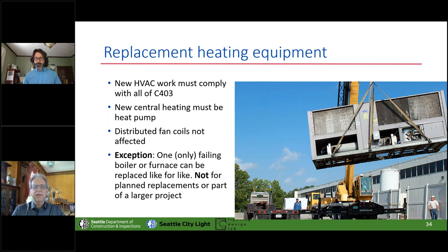For heating equipment, basically anything that's new must meet the new code. And if you replace the central heating system, it's got to be replaced with a heat pump. Now, at least for now, we've said if you've got one of these many Seattle towers with fan coils all around and a VAV reheat system, obviously you can't. We're not going to make people change out the basis of their whole mechanical design each time they remodel a floor, but that's a problem we're still working on.